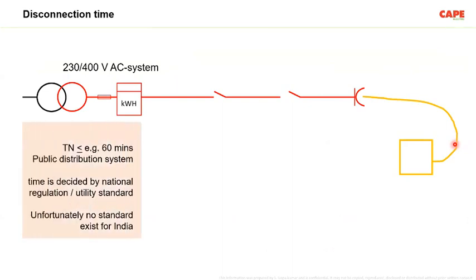Now, disconnection time. In almost every developed nation, what I am showing in the picture is the distribution transformer, a consumer premise having a meter, then inside the consumer premise the distribution, and finally the fixed equipment and the portable devices connected to this installation. Now, the disconnection time during a fault on the distribution is the responsibility of the distribution company.